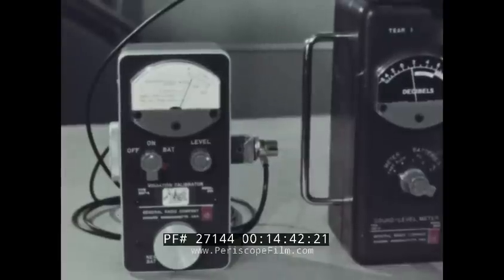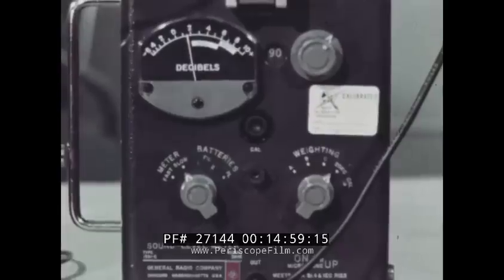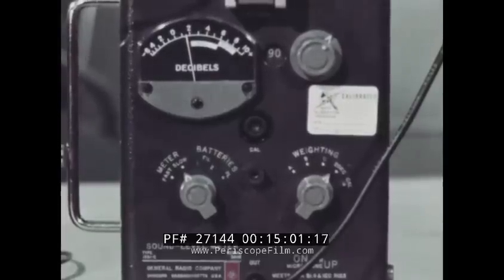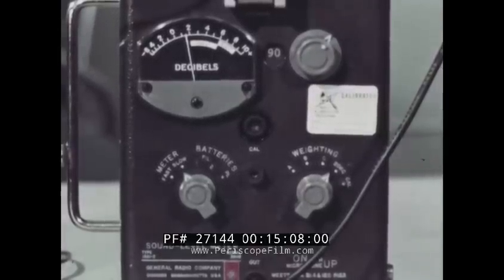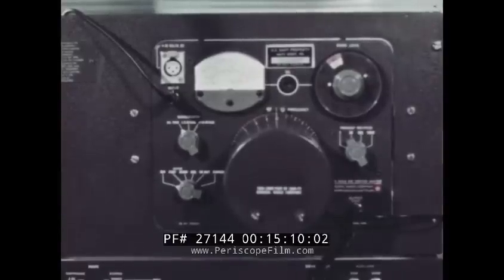The accelerometer converts the mechanical vibration of a machine to an electrical signal. Depending on the setting of the switch, the integrator alters the signal to provide a measure of acceleration, velocity, or displacement of the machine vibration. The dB levels of these 3 values are read from the sound level meter. These are broadband measurements.